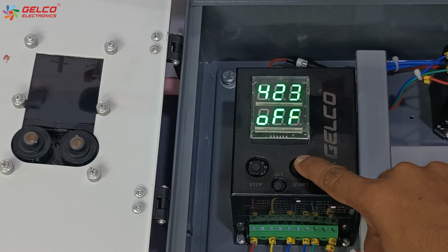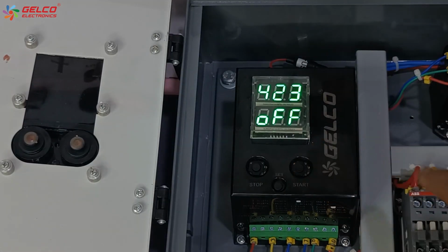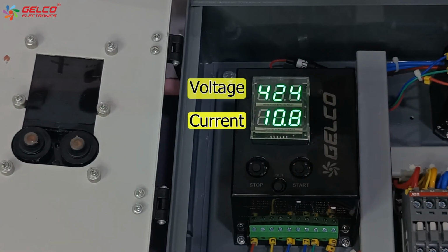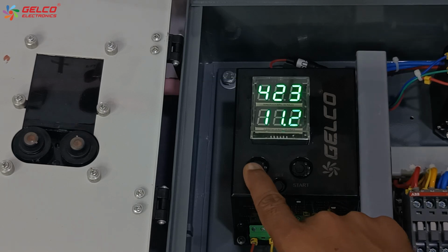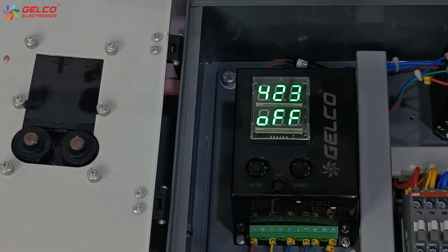Now turn on the panel by pressing the start button. We can see the voltage and current of pump on the display of panel. This current is the normal rated current of our pump. We need this normal rated current value during the parameter setting. Now stop the pump by pressing the stop button.